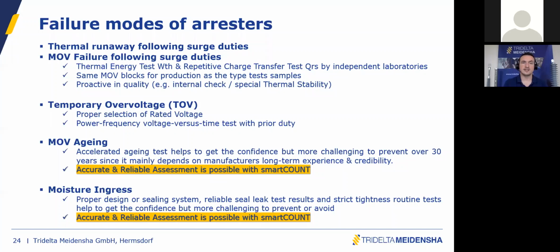But there are some failures that can follow surge duties, such as thermal runaway or MOV failures that have to do with the energy ratings I mentioned before. As a responsible manufacturer, we know how to prevent those failures with the type test, the quality control and the manufacturing process. We are also able to prevent failures due to temporary overvoltage with the proper selection of the rated voltage, and of course looking carefully at the type test results.